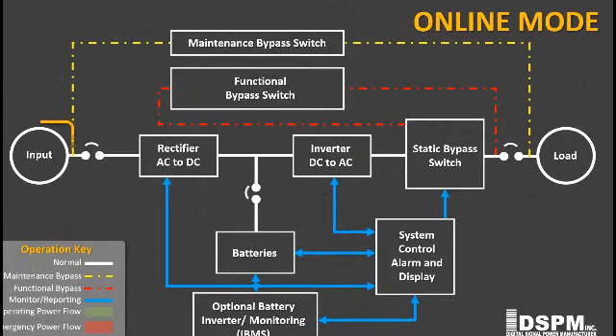Each DSPM inverter system is power insurance that sits between the utility company's power and your load. So let's walk through DSPM's technology with this very simple inverter system diagram. Of importance is DSPM's functional bypass switch that allows for the transfer of the utility company's power directly to your load. More importantly, when activated, it ensures no current is flowing through DSPM circuits, guaranteeing safe access for maintenance and service. Next on the illustration is the AC to DC rectifier stage, which converts the utility company's alternating current into direct current used to charge the batteries to full and ready capacity.